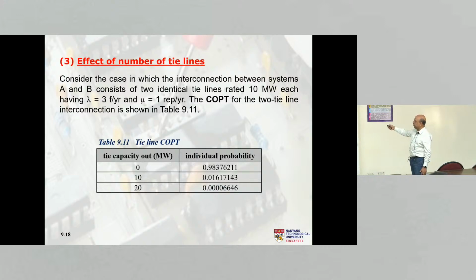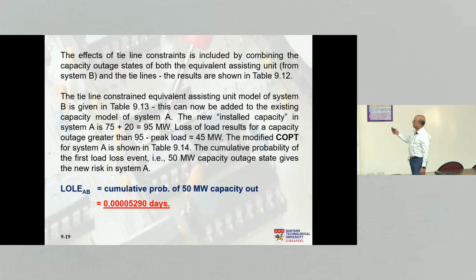We can actually get 20 megawatt over from system B. Previously, we were able to transport only 10 megawatt, but now we are able to transfer up to 20 megawatt. So this is the tie line capacity model, but we also have the model from system B. So the system B model has to go through the tie line model, and then you have to get a new model of the tie line constrained capacity outage probability table, correct? So that's what we do next.